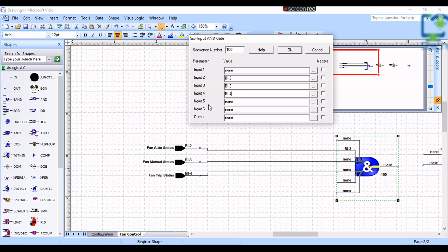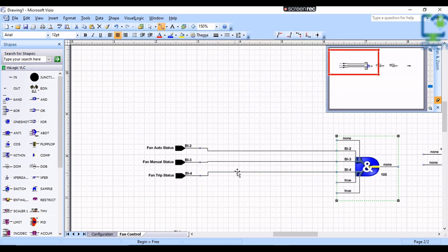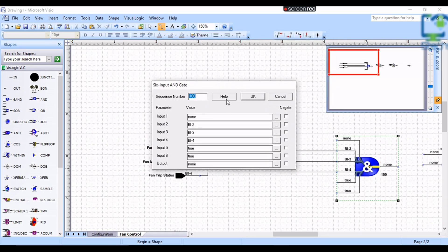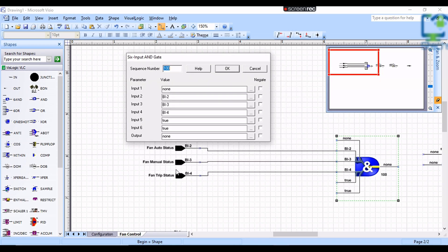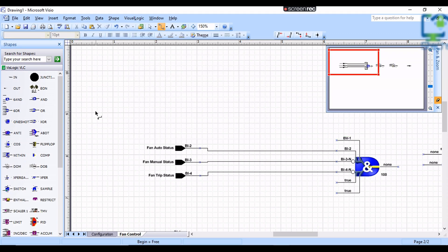Input 5 and 6 we need to write True, because these inputs are not used. Now, for normal operation, we have to reverse the values on manual status and trip status. So I am going to tick the Negate column for these two inputs — then it will show as On when these inputs are Off. Now I am going to give input 1 as BV 1 or Binary Value 1. It is a software digital point that I am going to use to control the fan from the BMS, so I gave the description as Enable Command from BMS.